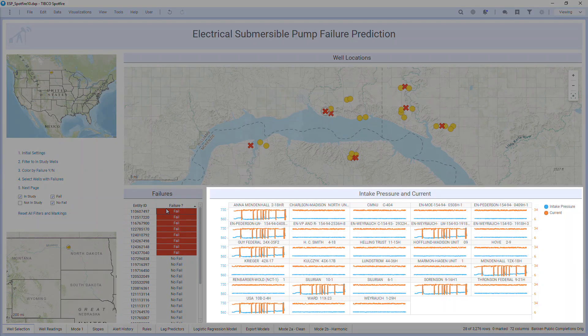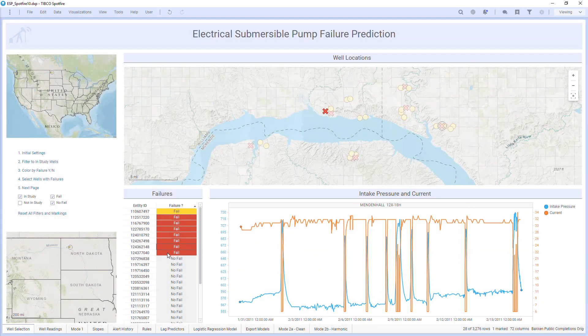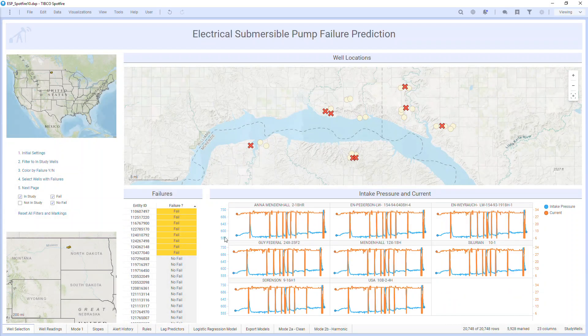At the bottom, I've brought in sensor data for electrical submersible pumps on these wells. For this demo, I just grabbed pump intake pressure, which is shown in blue, and pump motor current, which is shown in orange. Quickly selecting the wells with failure, I see that they have lots of spikes in their signals, which is something I want to investigate further.